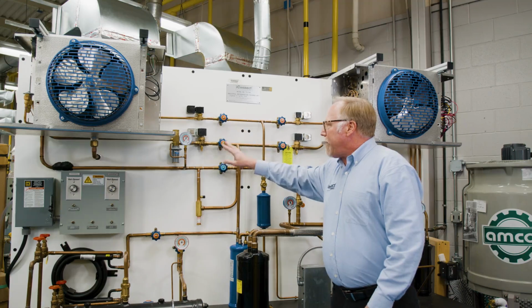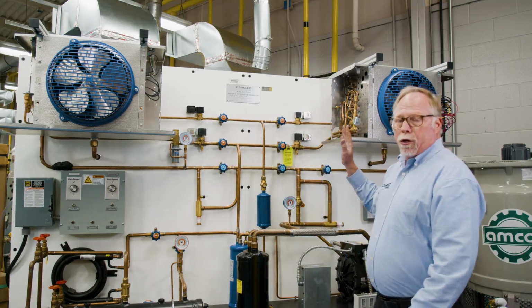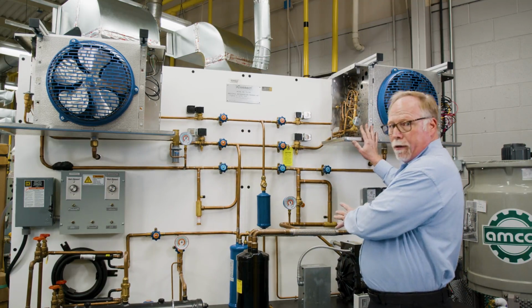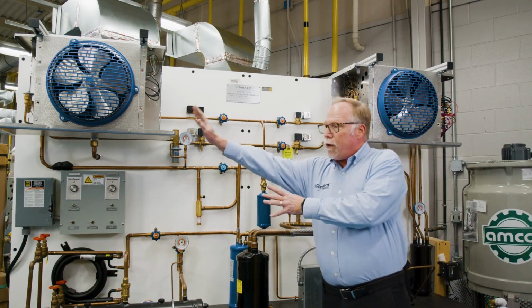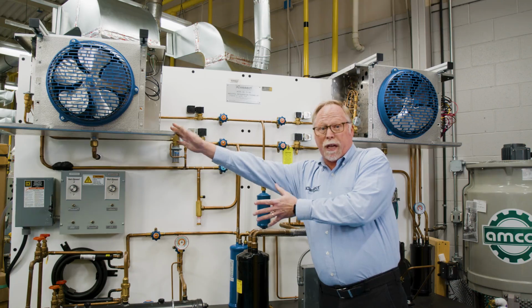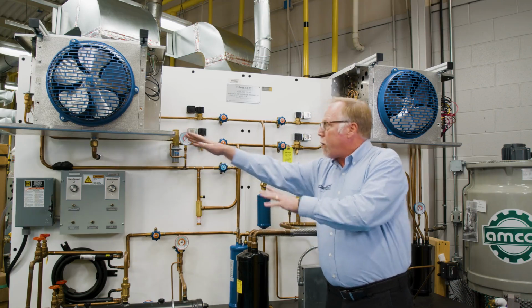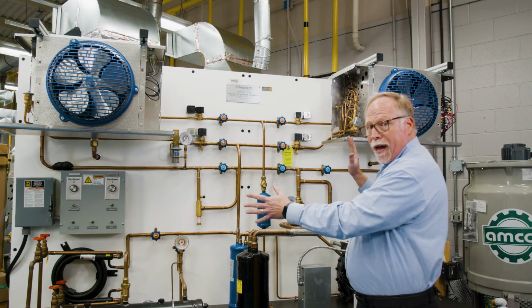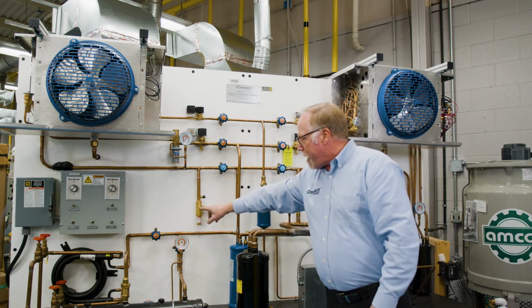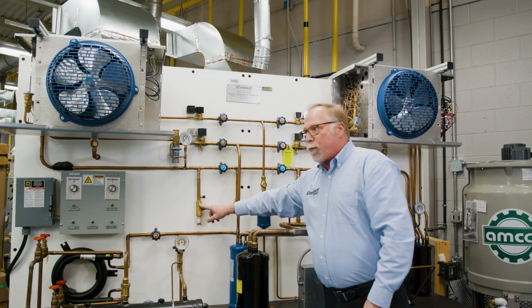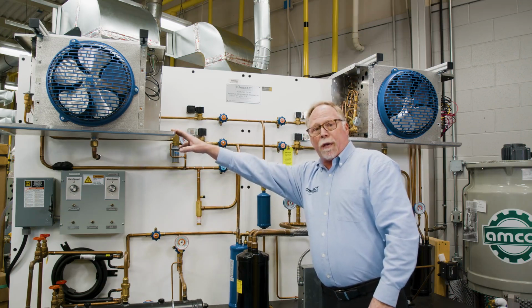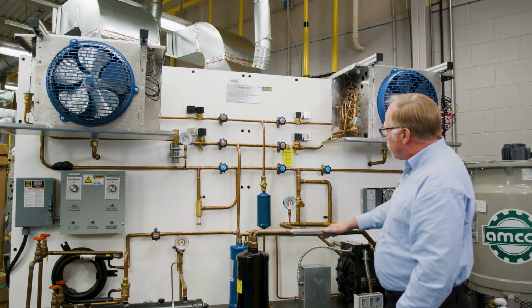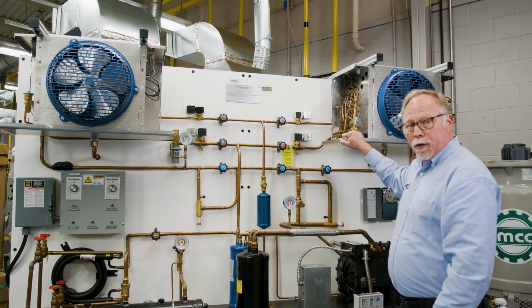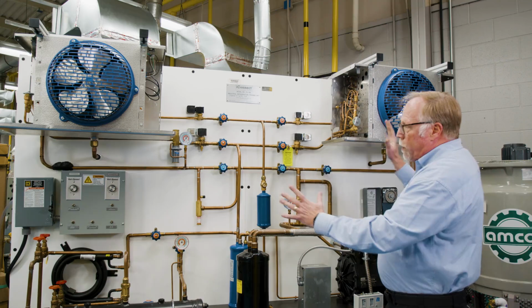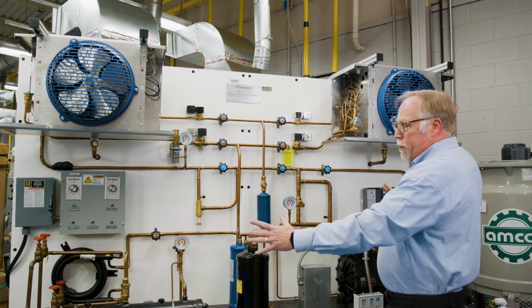Now here we have separate valves where we can actually isolate each evaporator coil. So you can make this a dedicated freezer. You can make this a dedicated refrigeration unit for a walk-in, like a walk-in cooler. Or you can make it a dual vap. And when you have a dual vap system, you can teach how important it is that we've got to have an EPR valve to maintain the pressure up on the medium temp coil while we're allowing the compressor itself to pull down number 2 freezer. So here we've got multiple concepts we can teach with just one training unit.